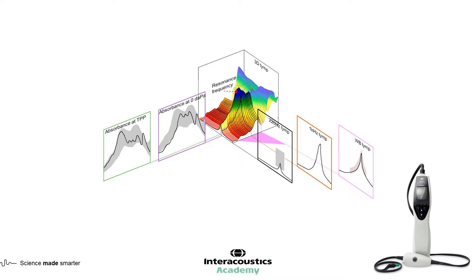A simple probe click covering the frequency range of 226 to 8000 Hz is used, instead of conventional tympanometry that uses a single probe tone frequency, such as 226 or 1000 Hz.